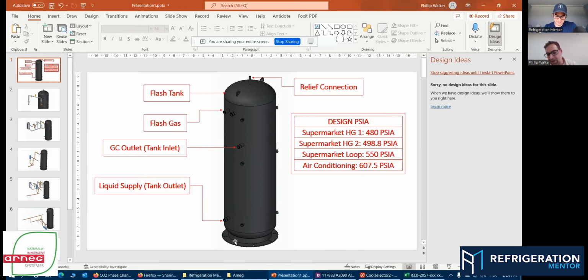The bottom base right here should be blown in. You get a lot of sweating occurring down here. Check your base, check your bolts. If they're starting to rust, maybe you're missing some blown-in insulation. So we take these flash tanks, we blow in polyurethane down here. We actually weld them right onto the skid of our machine. For a standard mechanical room, we have 1-inch insulation. A mechanical room that's going in a penthouse, we put 1.5-inch insulation. It's critical to the design of the flash tank. Improper insulation will cause an effect on your flash tank.